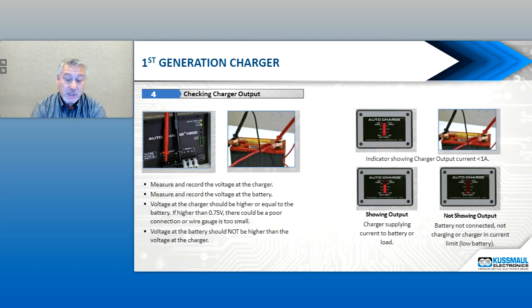If it is not showing anything, or it only has 1 bar on that bar graph, that's either going to indicate that the battery is not connected, or, say you have a 40 amp charger, that charger is pushing out 40 amps doing everything it can to try to keep those batteries charged, and it's just going to show that your batteries are low.